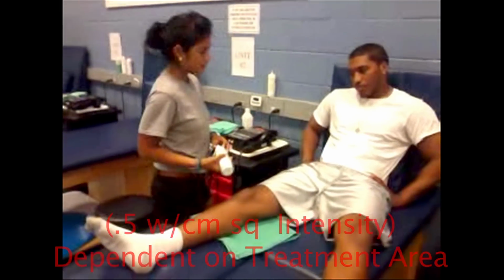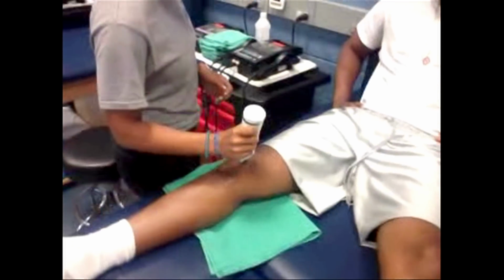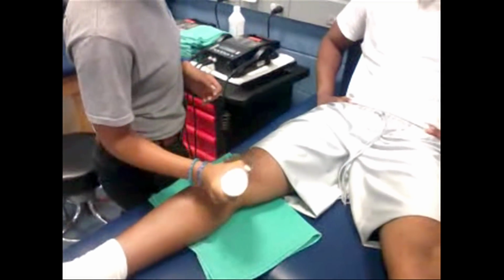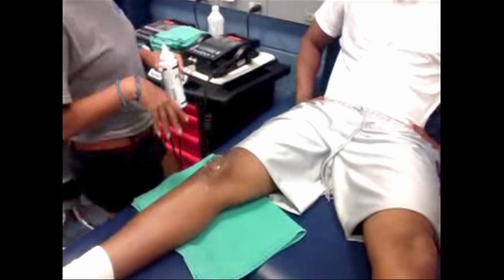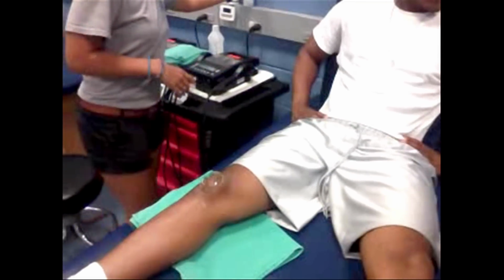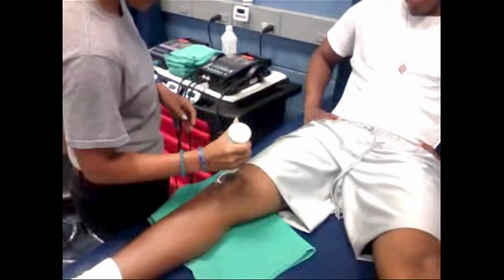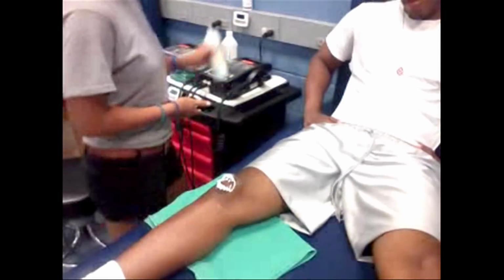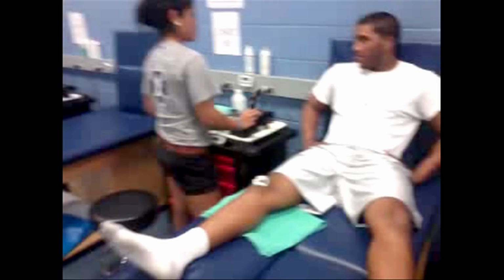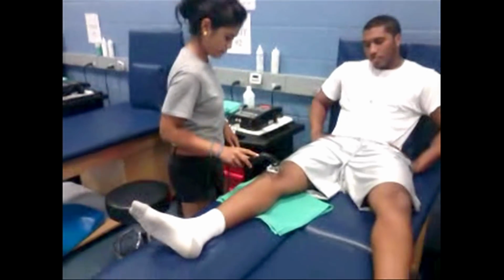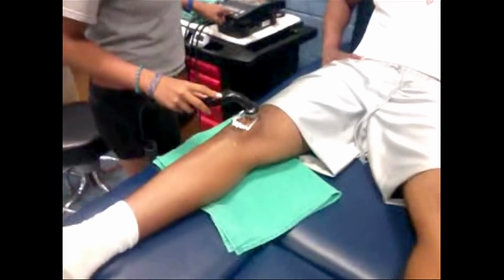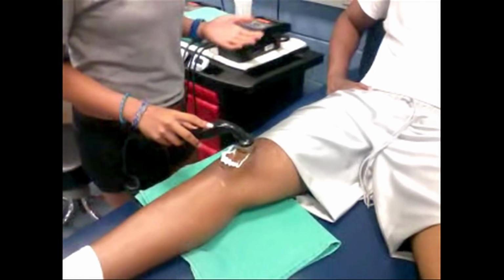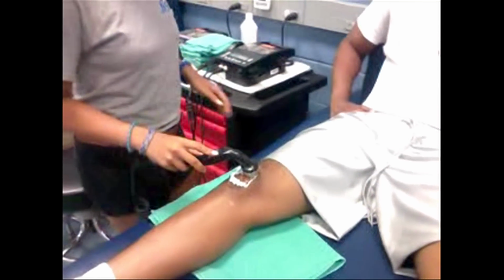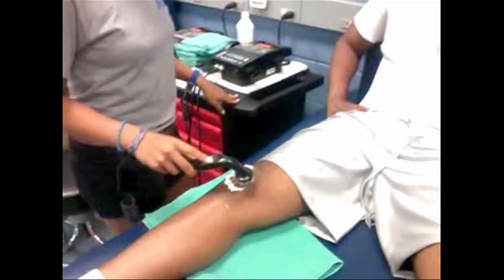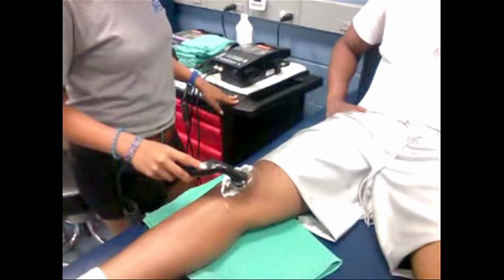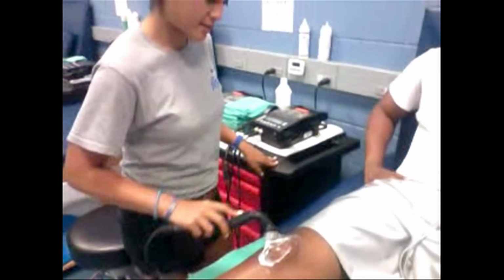Okay. So I'm going to be applying this ultrasound gel. It will help all the acoustic energy from the machine seep into the skin. And then I'm going to be applying the medication. Once that's applied, I'm going to take the transducer, place it, and set the parameters to continuous. I want it to be continuous so it has a thermal effect, since osteoarthritis is a chronic injury. I'm going to set the intensity to 0.5 watts per centimeter square because it is a superficial area.